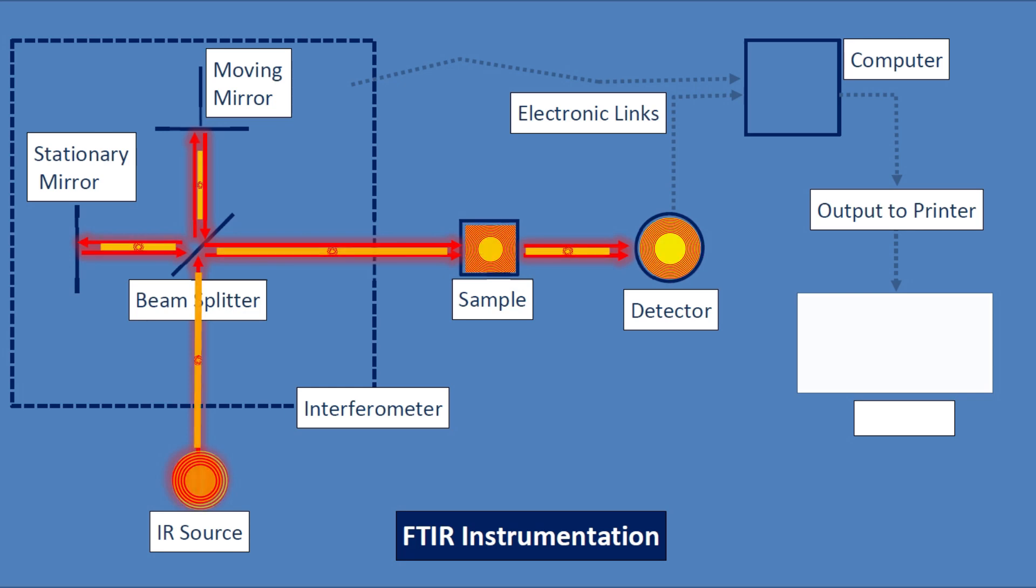When the radiation arrives at the sample, some frequencies are absorbed by the sample, and some are allowed to pass or be transmitted through the sample. When the transmitted radiation arrives at the detector, information about that radiation is decoded using a mathematical technique called a Fourier transformation. This provides information about the intensity of transmitted infrared radiation at each frequency separately.